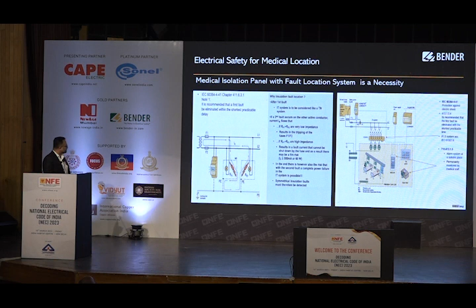And for group 0 and group 1 locations, where the insulation monitor and IT system are not there, instead of an RCD, which everybody discussed, we are proposing and supplying in some hospitals residual current monitoring. Instead of tripping, it continuously monitors the leakage currents from as low as 5 milliampere, and you can set any tripping value and alarm value in this type of system. It is called 24/7 monitoring.